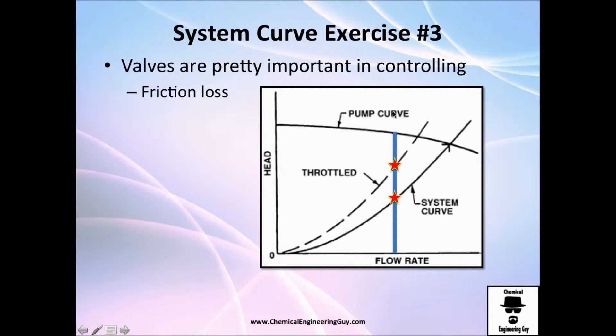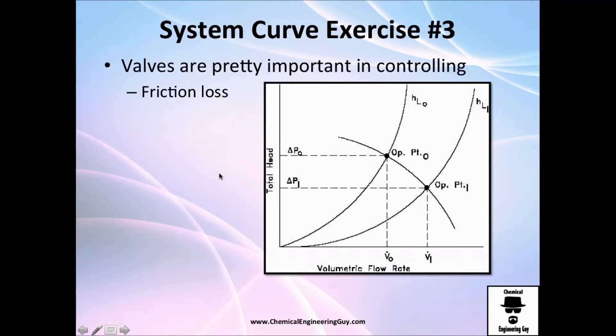This right here just to show you that for the same flow rate I got different pump requirements. So of course if I close a little bit or I throttle the valve, I will increase the pump requirement. The same goes right here. Let's say we have this operation point - operation point zero is very optimal. Let's say efficiency is very high, we require less horsepower to operate, we require less maintenance, we have a net NPSH acceptable.